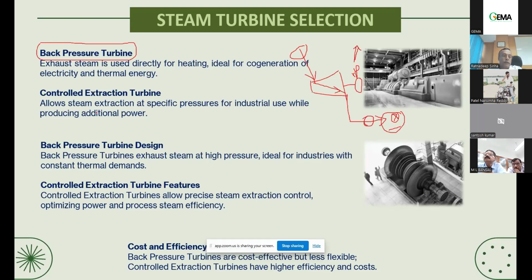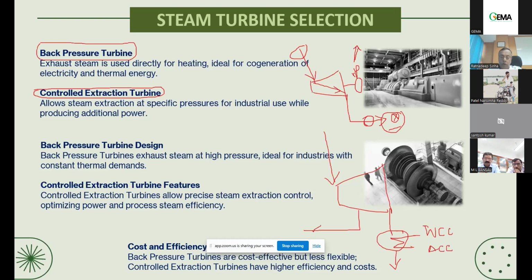Now, in a controlled extraction turbine, steam is extracted. What is controlled extraction? It is a steam turbine where you give the main steam, and here you have a condenser where you are condensing through cooling water, or you can think of an air cooled condenser. So there can be a WCC or ACC based on your water requirement, and we take extraction from the steam turbine.